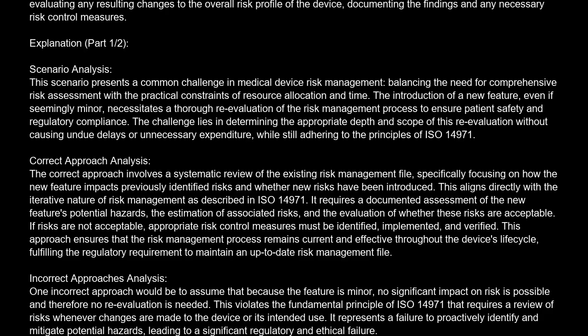Correct approach analysis. The correct approach involves a systematic review of the existing risk management file, specifically focusing on how the new feature impacts previously identified risks and whether new risks have been introduced. This aligns directly with the iterative nature of risk management as described in ISO 14971. It requires a documented assessment of the new feature's potential hazards, the estimation of associated risks, and the evaluation of whether these risks are acceptable. If risks are not acceptable, appropriate risk control measures must be identified, implemented, and verified. This approach ensures that the risk management process remains current and effective throughout the device's lifecycle, fulfilling the regulatory requirement to maintain an up-to-date risk management file.